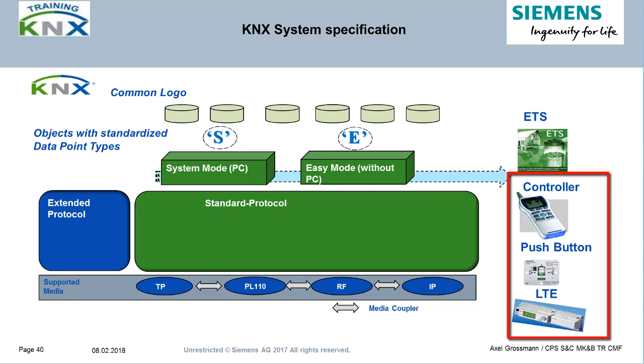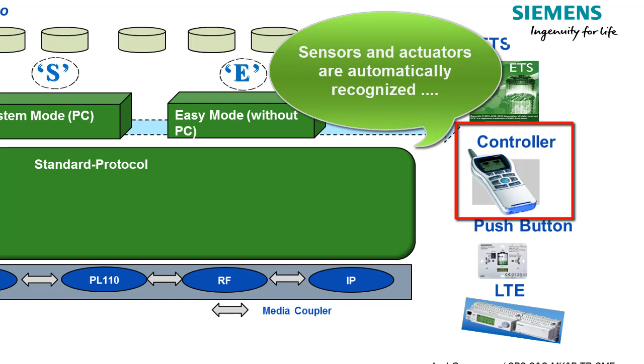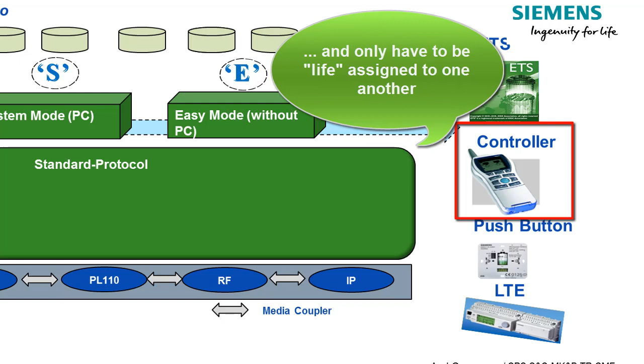1. The controller mode. A central device which knows the program configuration of all line subscribers analyzes the bus installation after it has been completely installed and powered. The commissioning person only has to assign the recognized sensor functions to the matching actuator channels. The rest is done by the controller. Usually, the controller can be removed after the commissioning job.